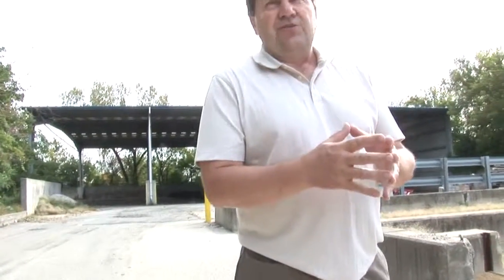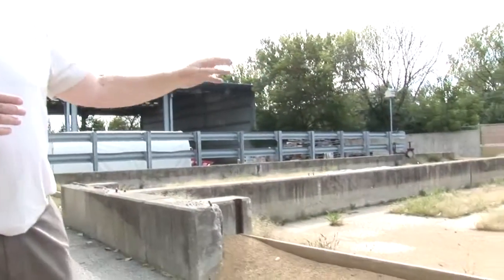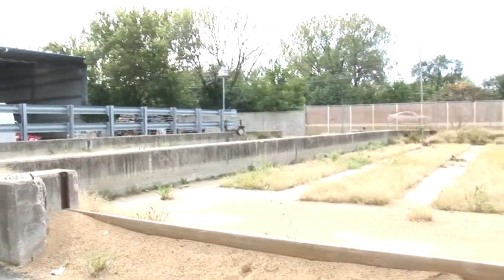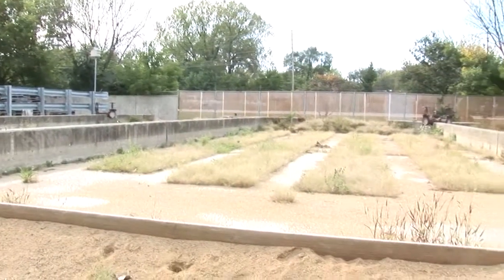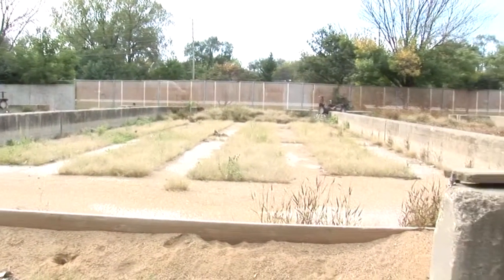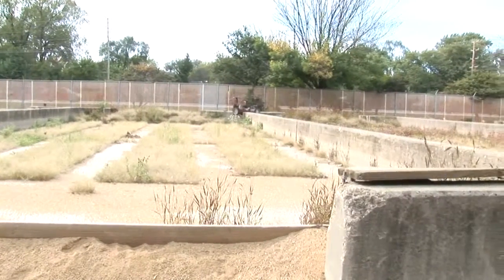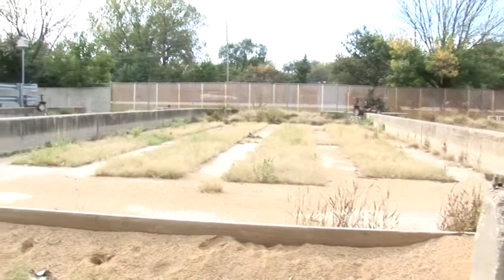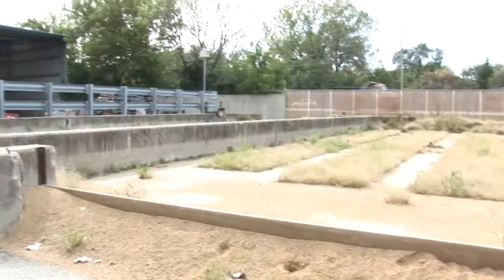Now, if our belt press should break or we need extra storage capacity, we do have drying beds available. However, the drying beds are not cost effective. The cost of the sand and the material and the labor to process sludge through the drying bed is cost prohibitive compared to running the belt press. The belt press is more efficient. For the same material dollars, we get 5 times the volume of sludge by running the belt press.